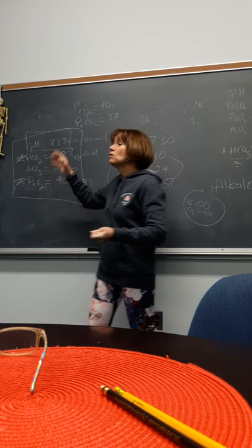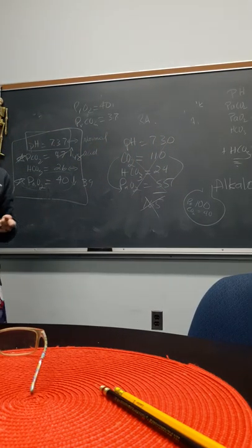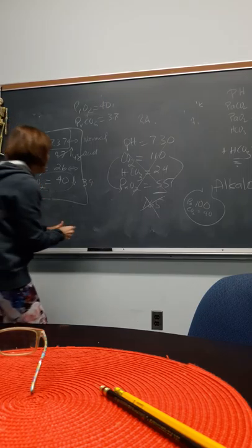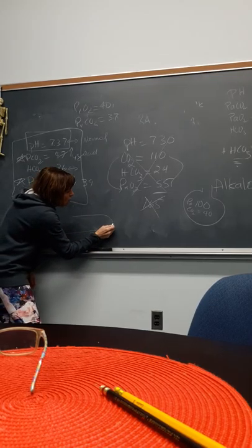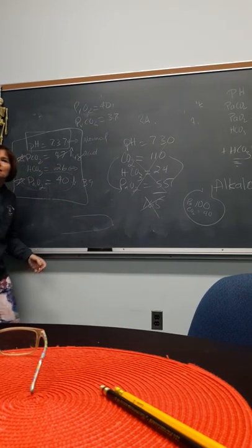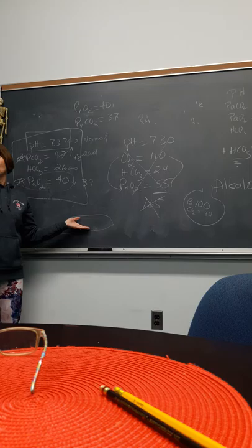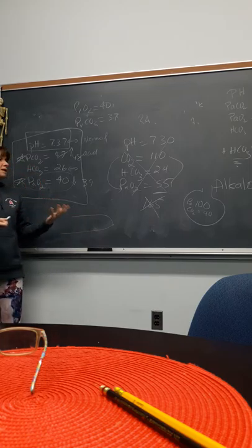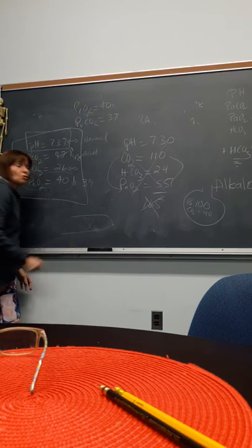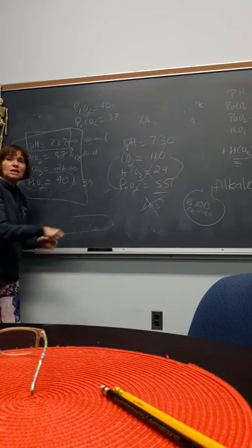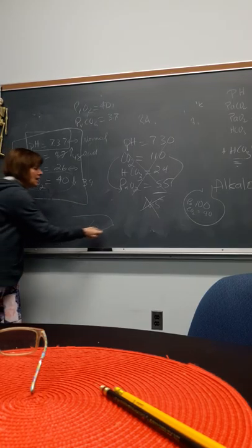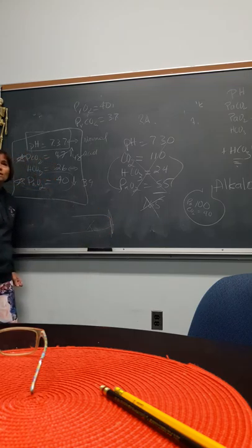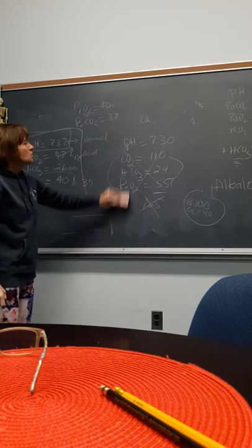A lot of times, remember, you've got those four electrodes, right? Blood is a protein. Most of the time, the blood gets stuck on an electrode. So here's my little electrode. All I need is a little bit of blood to get stuck there, and it's going to throw my electrode off. So we rinse it a few times. If that doesn't work, maybe my electrode is old, or the solution in there needs to be changed, but something is saying, here's my electrode that determines my values, and it's not coming in right now. Does that make sense? Okay, good.